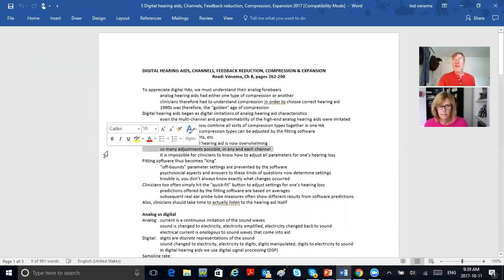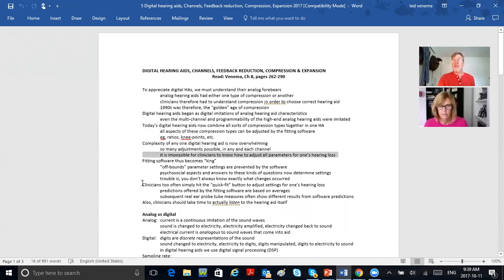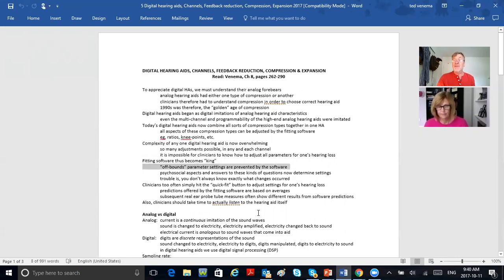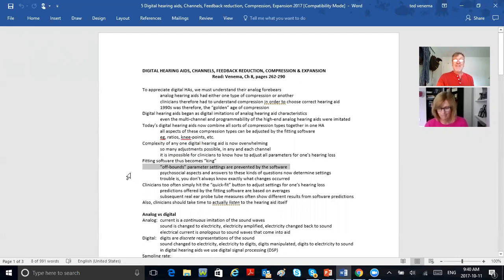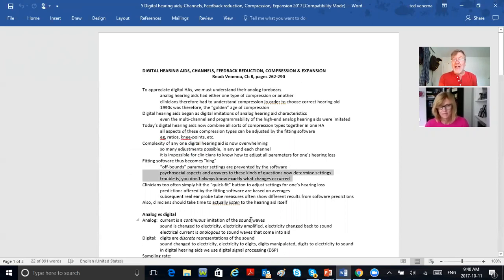So many adjustments are possible in each and every channel that it's impossible for clinicians to know how to adjust them all for the hearing loss, so the software has become king. Off-bounds parameters are now prevented by the software. Psychosocial aspects and answers to kinds of questions now determine settings.